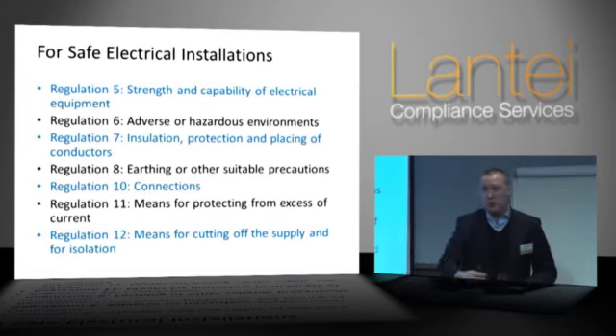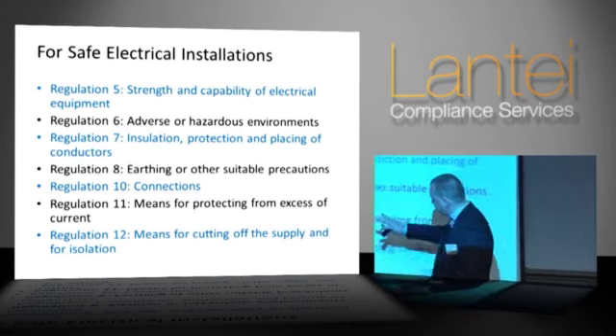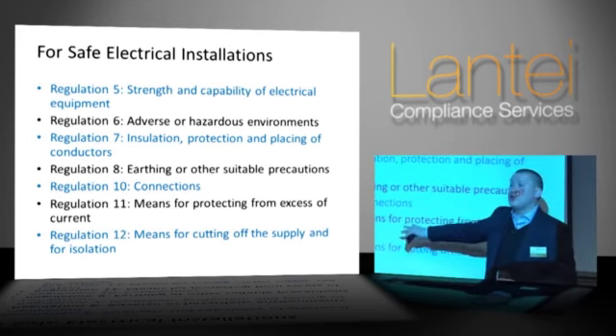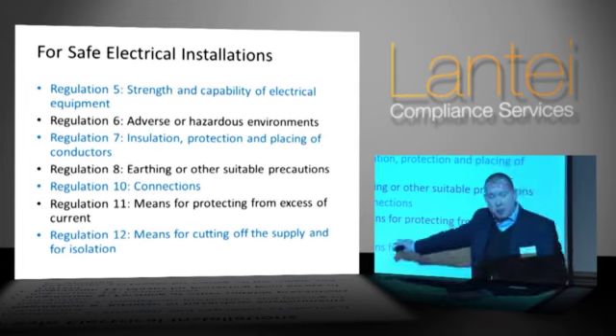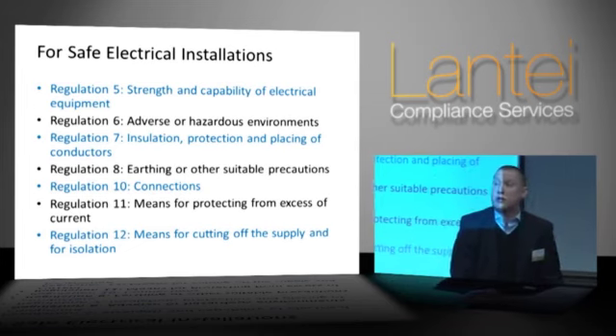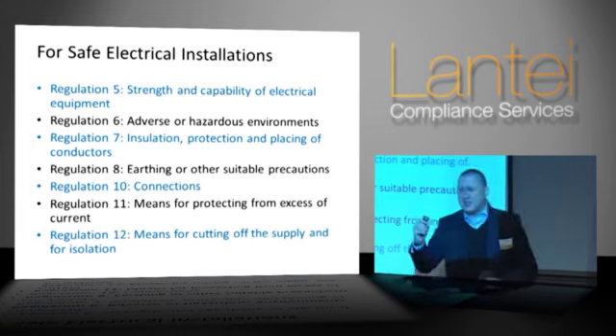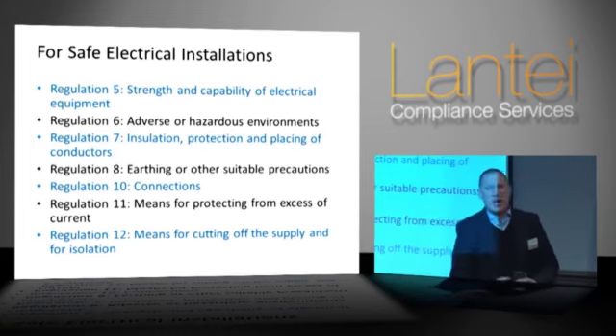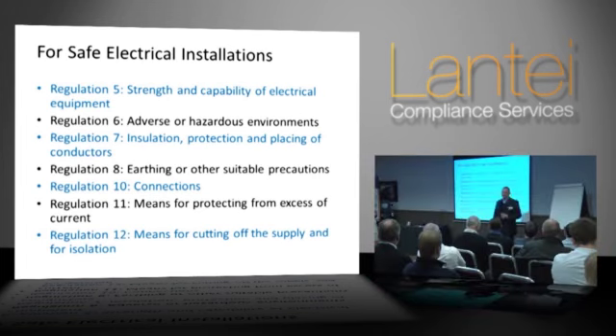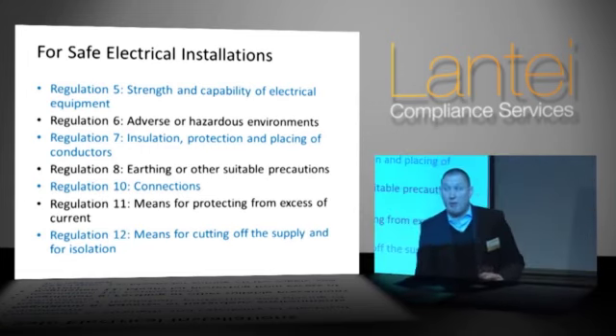As an example, most of you will probably have seen something like this before: on the wall we've got an isolator, a 100 amp isolator, controlling, let's say, a motor. What's going to happen, ladies and gents, to that isolator if the motor pulls, say, 130 amp? What do you think is going to happen to it? It's not a protective device, is it — it's an isolator, don't forget. It's just going to get warm, isn't it. We go up to it, touch the side, and we're going to feel a warmth there. Now, what's going to happen to our 100 amp isolator if the motor's pulling, say, 250, 300 amp?